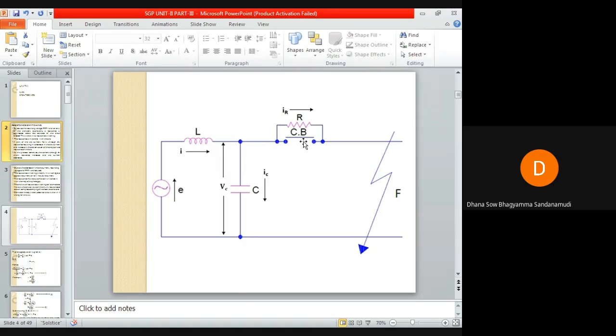Resistance switching is usually used to interrupt the capacitive currents of the circuit as well as low inductive currents of the circuit. Resistance may be automatically switched in with the help of spare gaps. Spark gaps means two spheres with a gap, connected within the circuit.